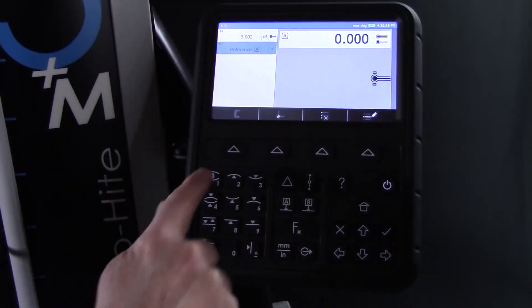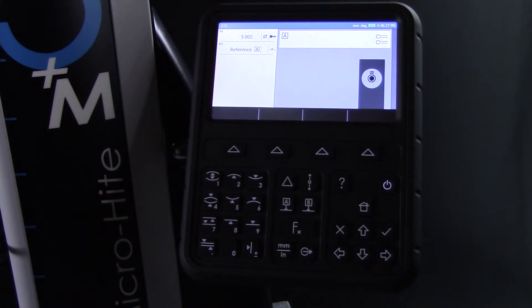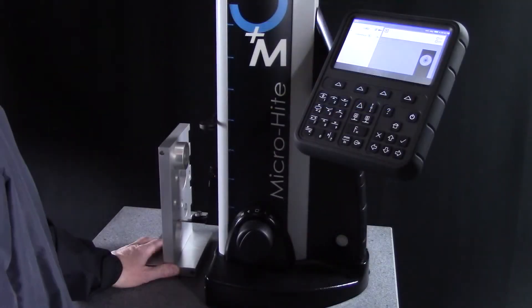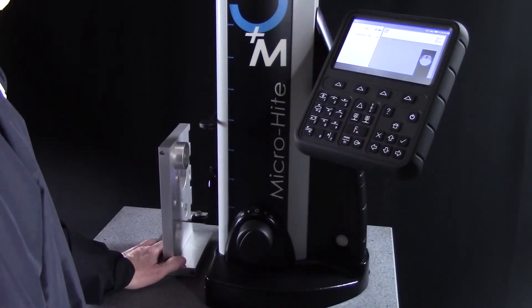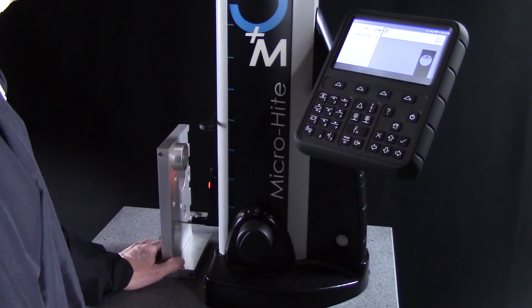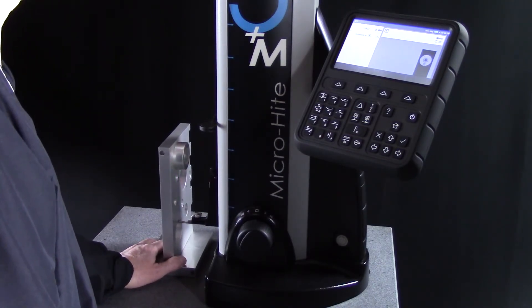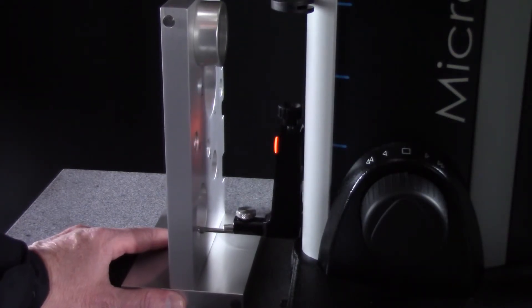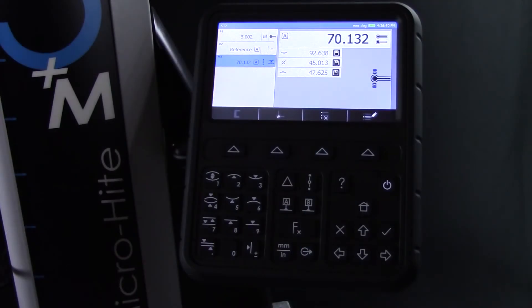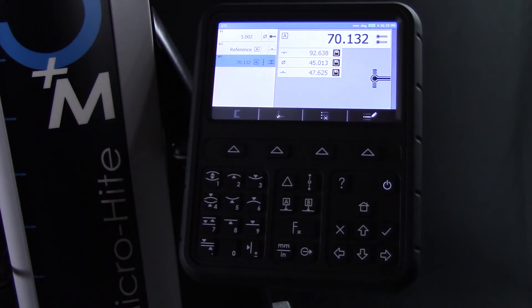Now I'll measure the top and bottom of this bore by selecting the automatic bore measurement button from the measurement zone on the keypad. I'll sweep each surface so that the gauge can determine the high and low point. When the measuring process is complete, the centerline measurement is displayed. In addition, the display shows the measurement to the top of the bore, the bottom of the bore, and the difference between these two measurements.